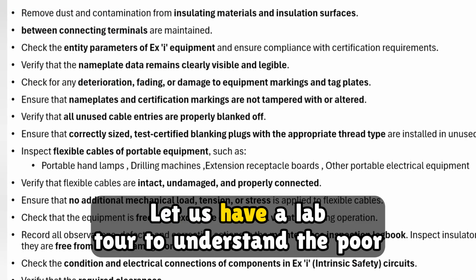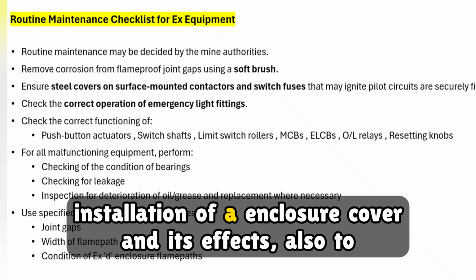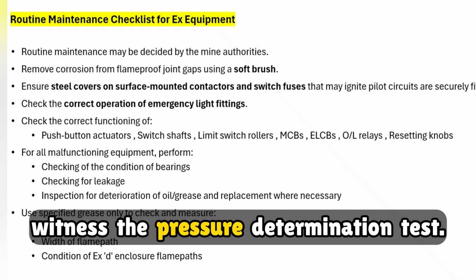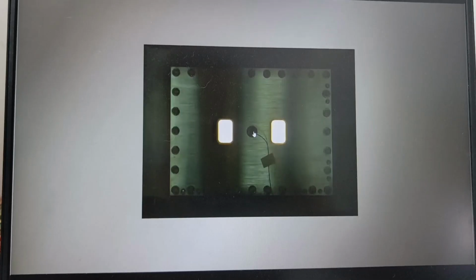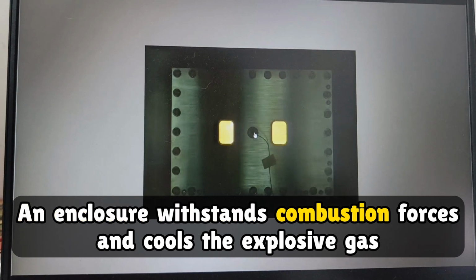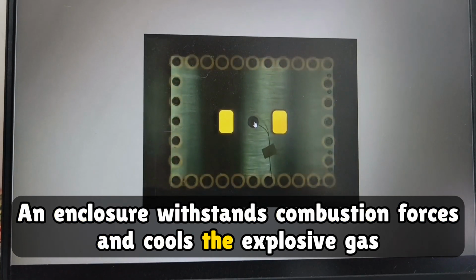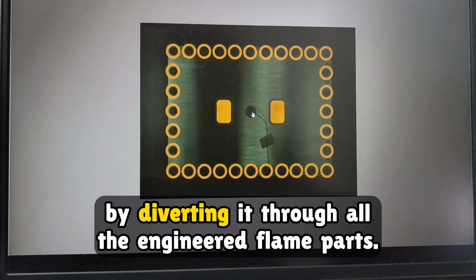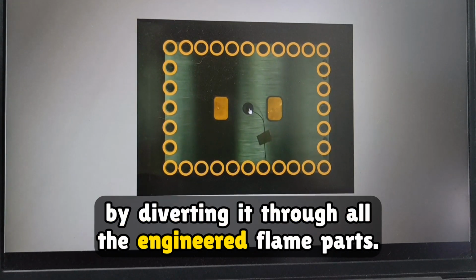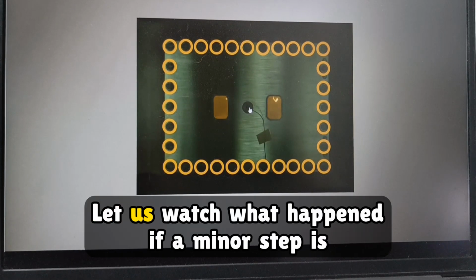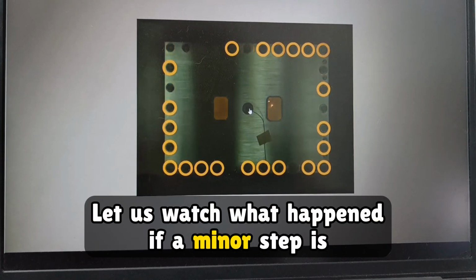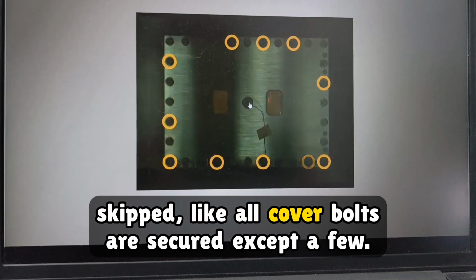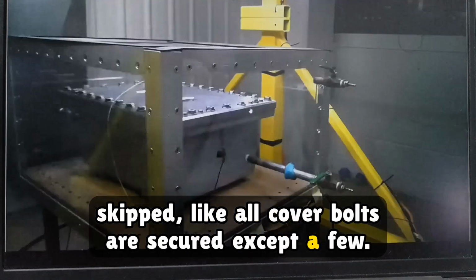Let us have a lab tour to understand the poor installation of an enclosure cover and its effects. Also, to witness the pressure determination test. An enclosure withstands combustion forces and cools the explosive gas by diverting it through all the engineered flame paths. Let us watch what happened if a minor step is skipped, like all cover bolts are secured except a few.